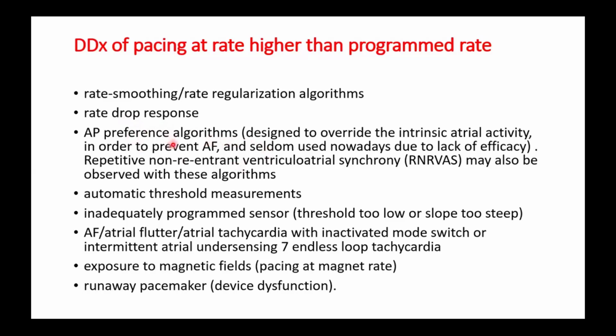Also, some algorithms to prevent AF tend to perform atrial pacing at a rate higher than the intrinsic rhythm to reduce the incidence of AF. However, studies found that this is actually not effective. Also, when you program auto capture, you may incidentally see this during auto capture testing, so you detect a rate higher than the programmed lower rate. Or when you are turning the sensor on and programming it very sensitive, or programming the threshold of intervention at a very low level. Or when a tachycardia, atrial high rate, or pacemaker-mediated loop tachycardia occurs.